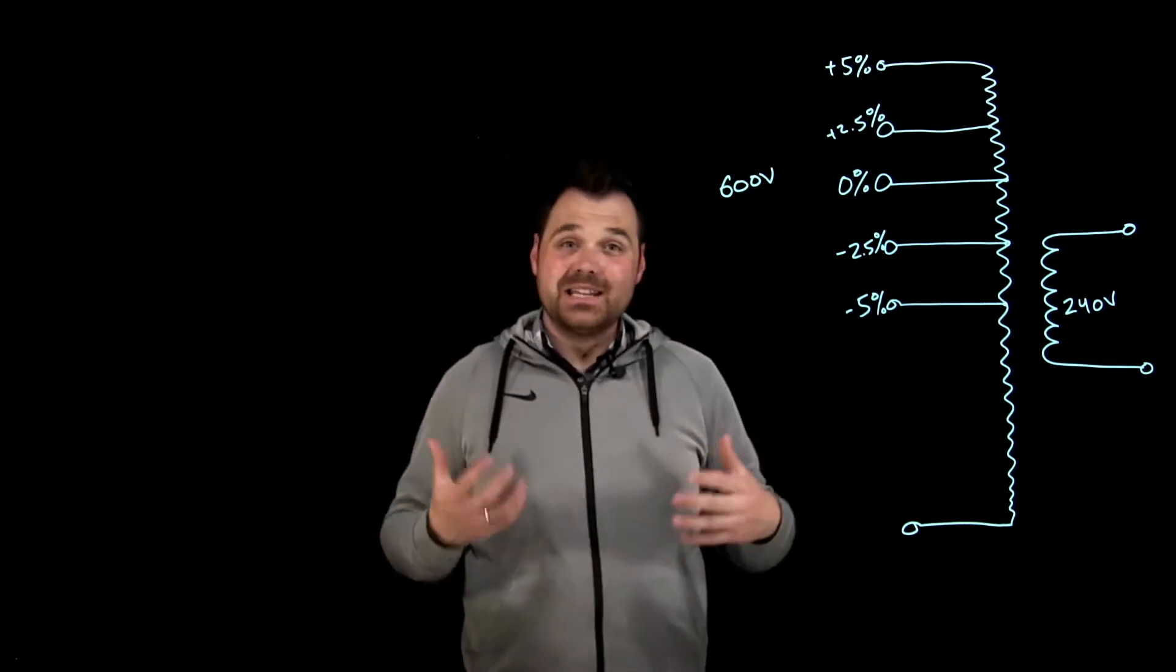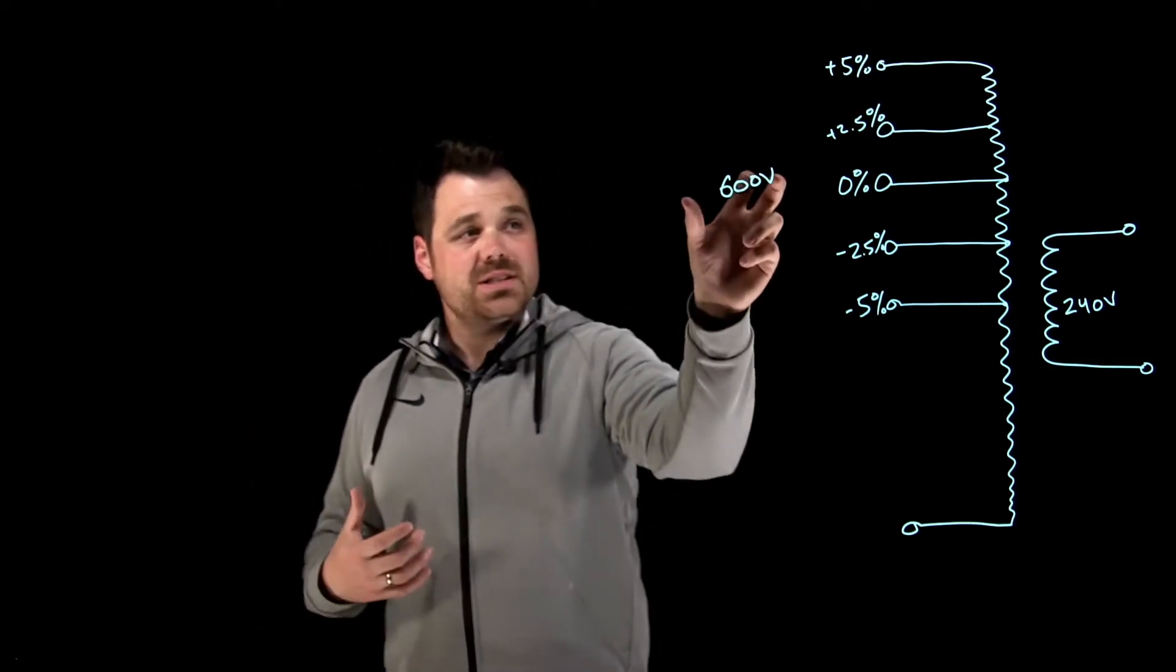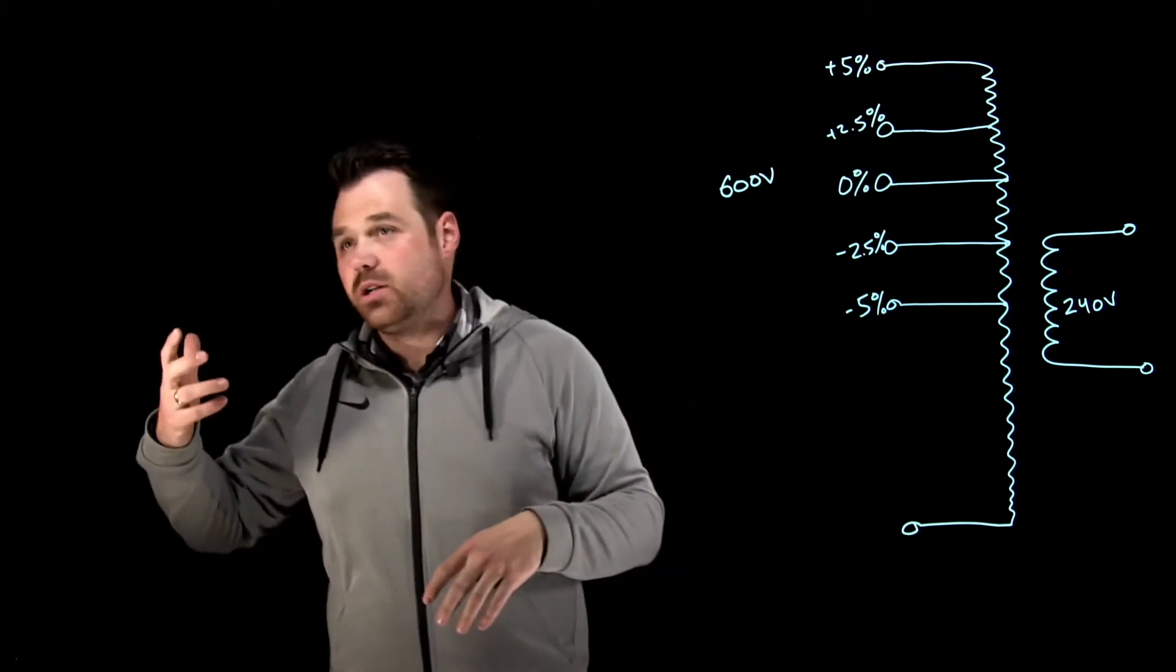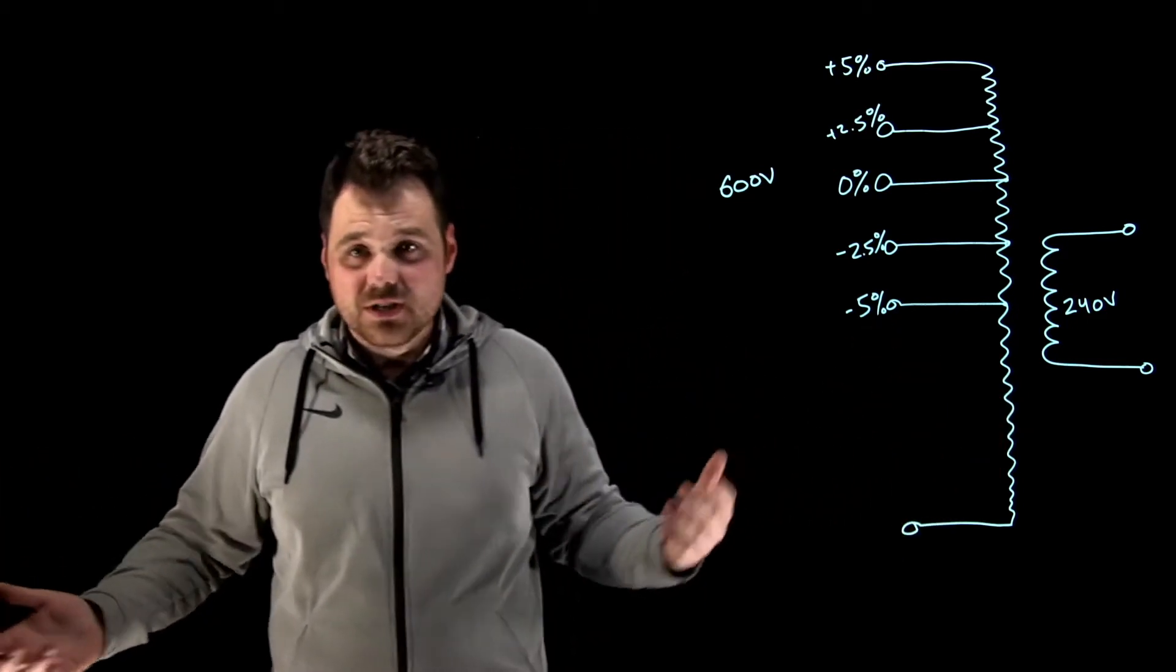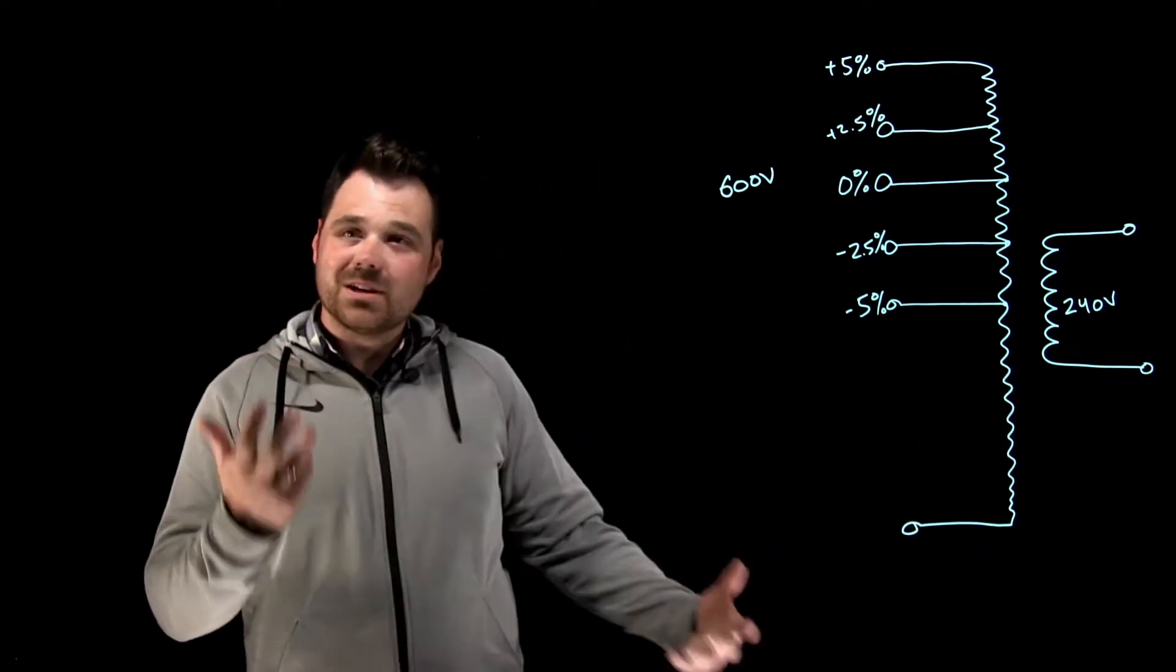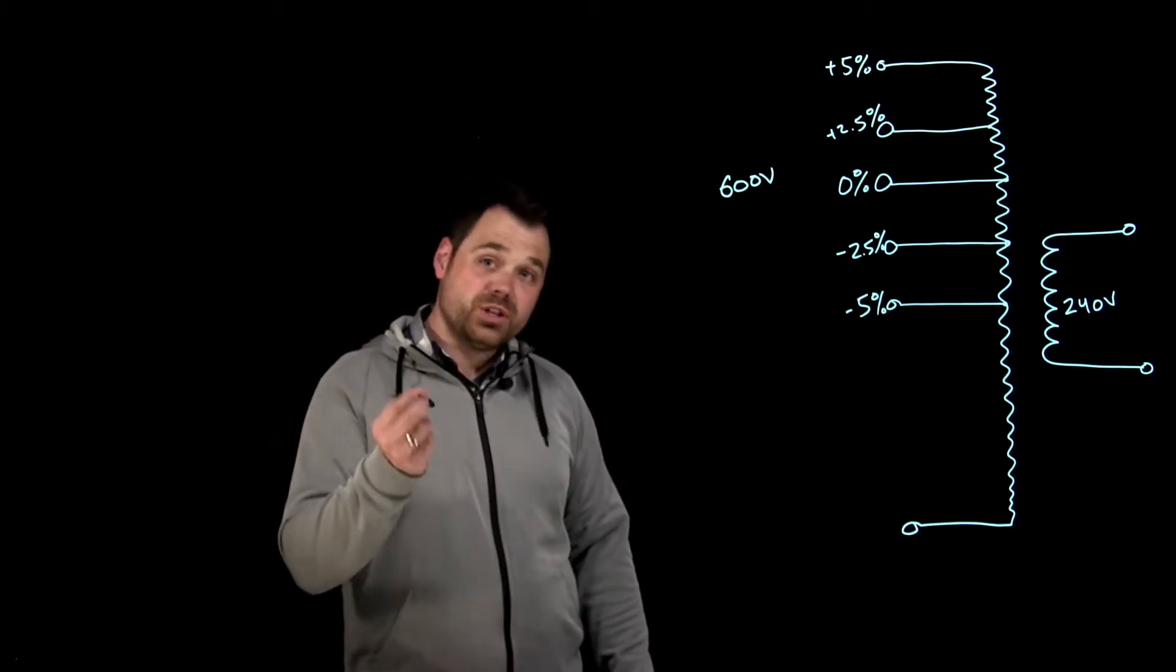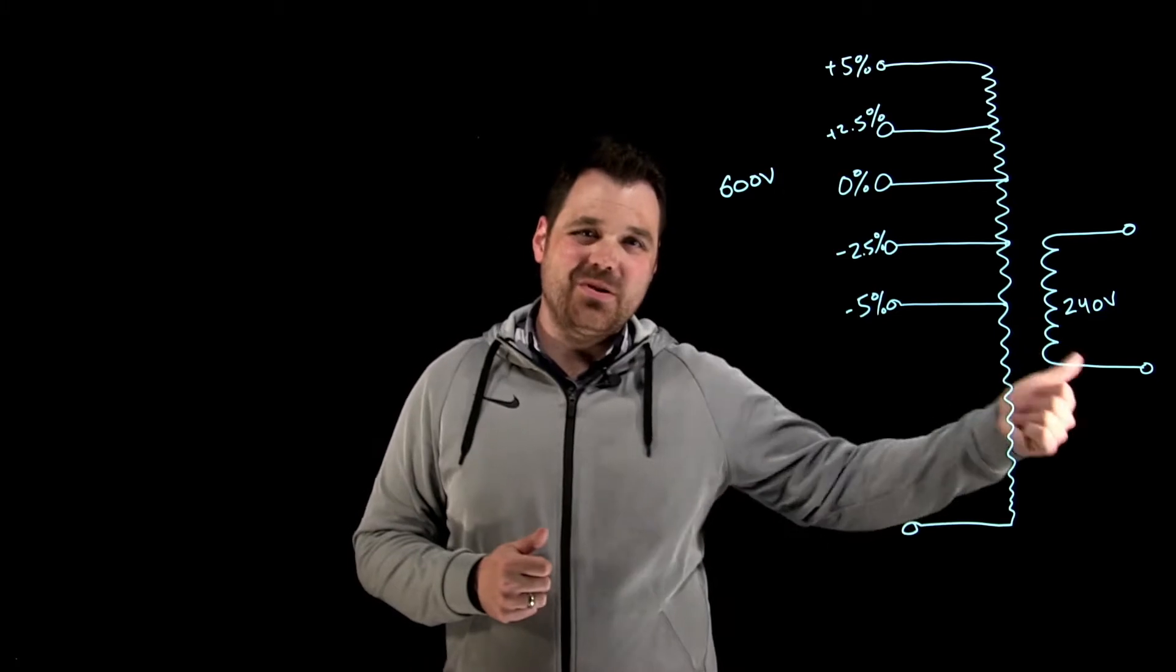Well, they are there in case my primary voltage isn't quite right. So this is a 600 volt primary. What if I only had 570 volts? What if I had 620 volts? If your primary voltage isn't right, your secondary voltage isn't right. So some transformers have these primary voltage taps, so that we can adjust the voltage on the primary, so that we still get our rated secondary voltage.